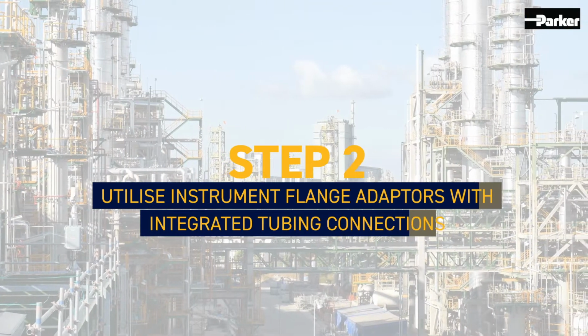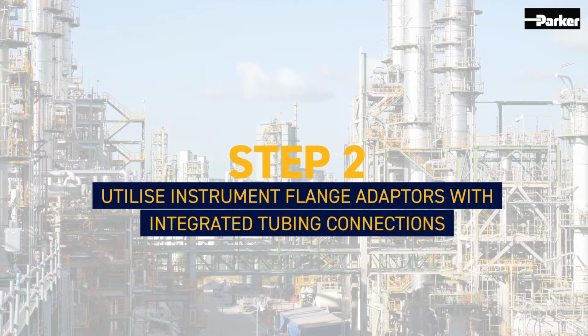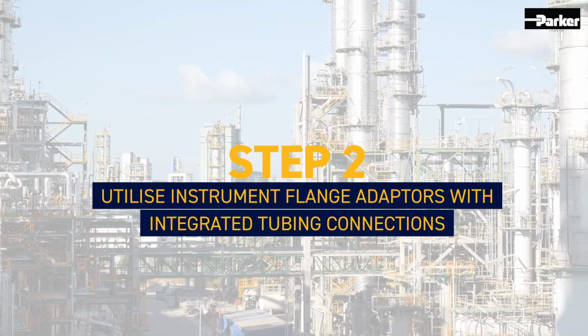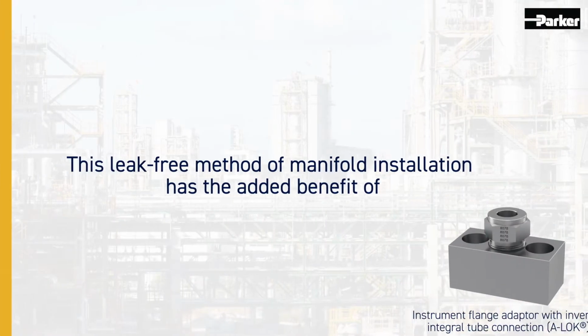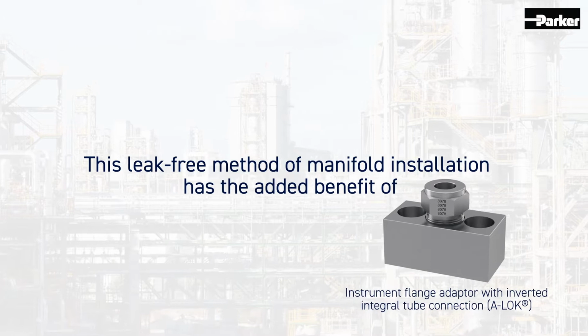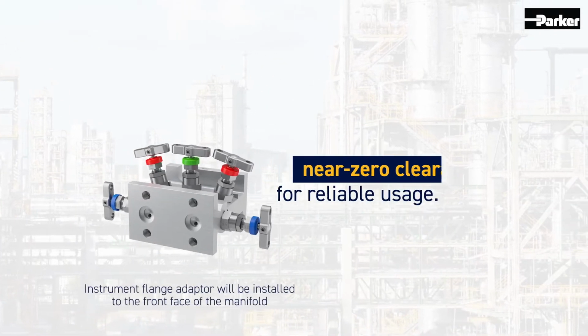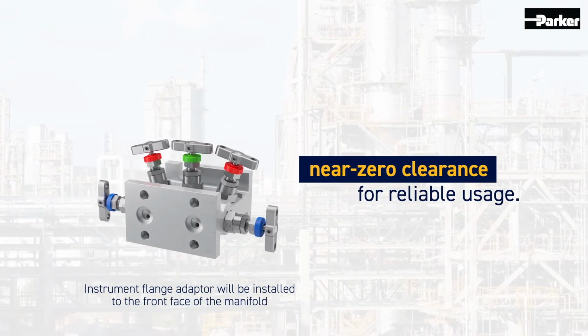Step 2. Utilize instrument flange adapters with integrated tubing connections. This leak-free method of manifold installation has the added benefit of near-zero clearance for reliable usage.